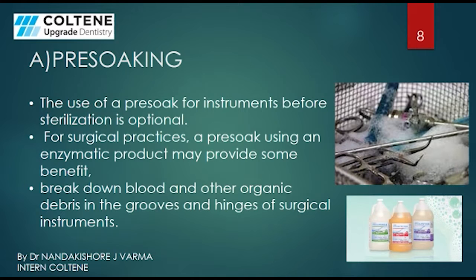Pre-soaking. Yes, it can be said to be an optional step in the process of cleaning or decontamination. As we said in the previous slide, if we are not able to clean contaminated instruments as soon as possible, we have to soak them in an enzymatic solution. Why should we do that? To prevent the drying of blood and debris. It also helps in breaking down the blood and organic debris in the grooves and hinges of surgical instruments, which helps in better cleaning.